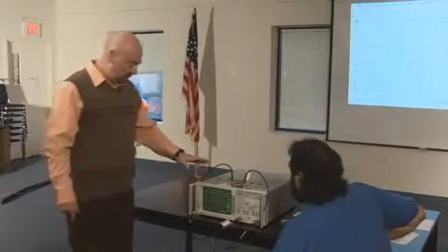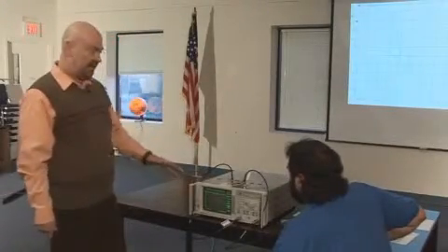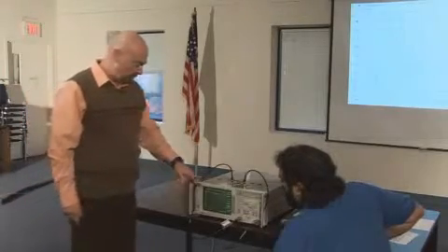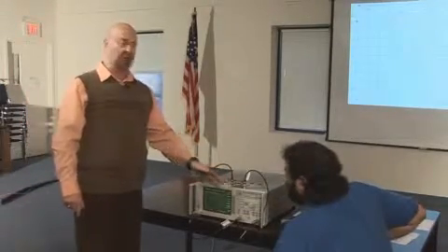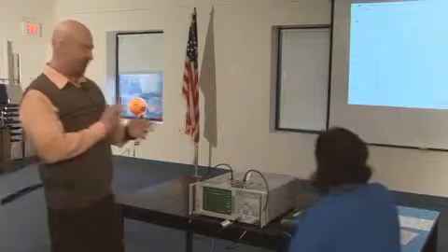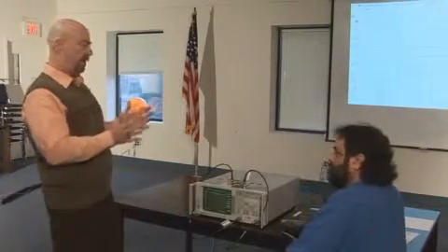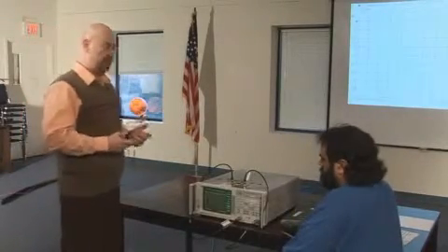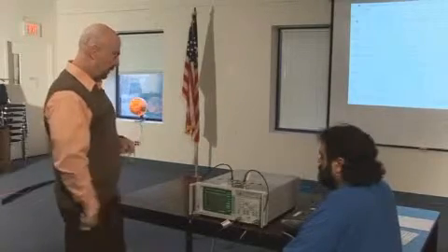Now I have this network analyzer set up to read in 10 dB increments. Obviously a short falls right at the 0 reference marker, which means nothing is happening to it. All your power out is flowing straight through and you're receiving all your power in on the other port.